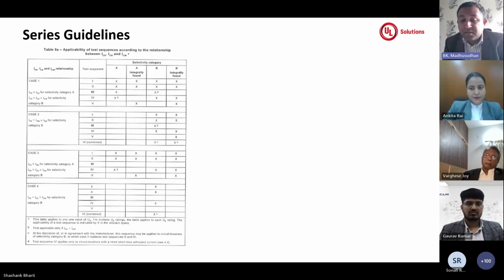So some of the sequences can be waived off, especially sequences 4 and 5. In the majority of cases these tests are not applicable, because when category B has been declared for a breaker, and it has the same short circuit ratings as category A, then the majority of these tests can be waived off based on the standard requirements. Next slide, please.